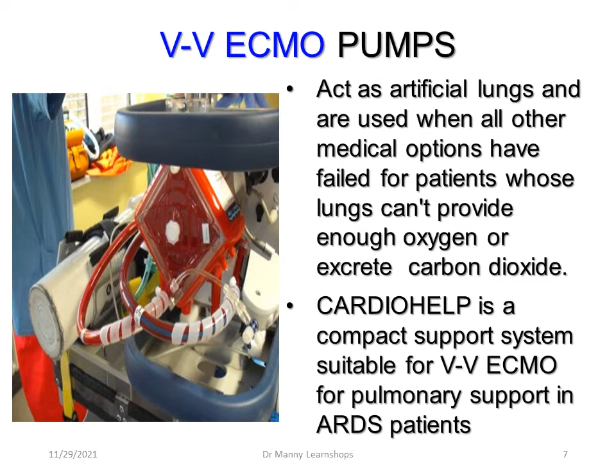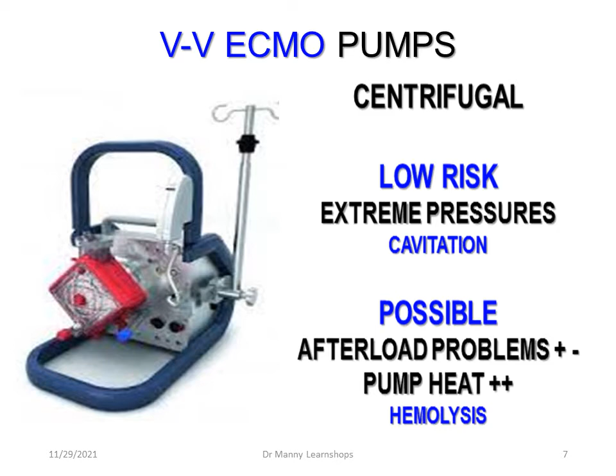But from my career perspectives, it's a very important, friendly, helpful, effective pump. Now, it's also centrifugal, which means there's a low risk of extreme pressures and the causing of cavitation, which basically means extracting air out of the blood, causing a potential air embolism. Possible afterload problems could occur. The pump could heat, which can promote hemolysis, but this can happen in all pumps as a result of malfunction or ineffective switches. When it comes to the gas exchanger, the extracorporeal gas exchange is with a membrane oxygenator.